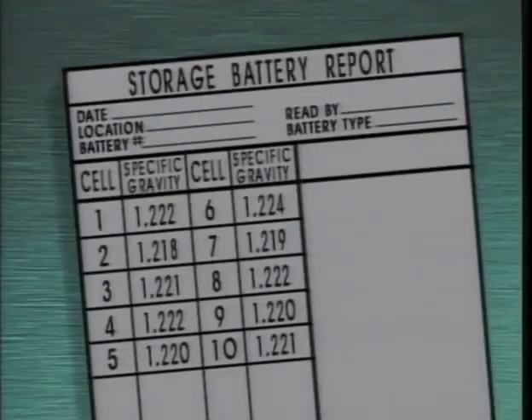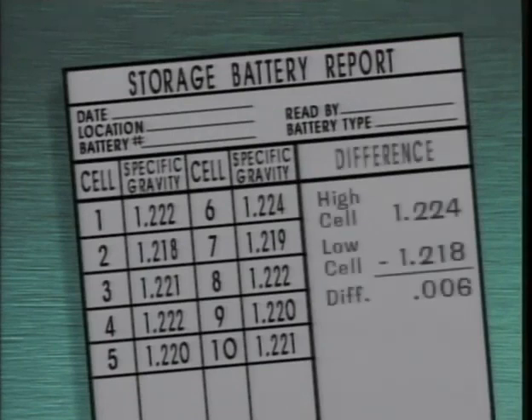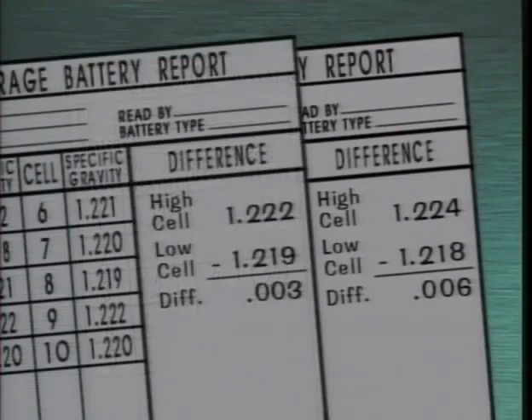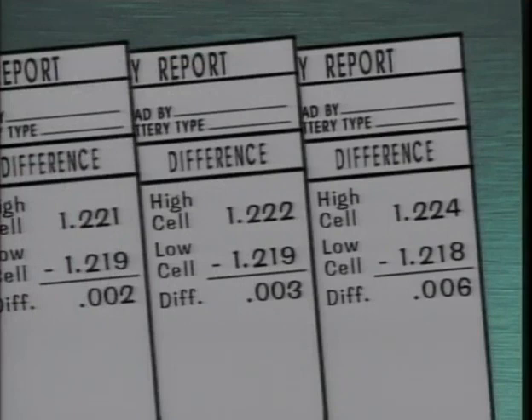After cell specific gravities are corrected for temperature, they can be evaluated in several ways. One way is to identify the highest and lowest cell specific gravities and determine the difference between them. The difference is compared to high and low cell specific gravities from previous tests. A noticeable increase in the differences may mean an equalizing charge is needed to raise the specific gravity of the weaker cells.